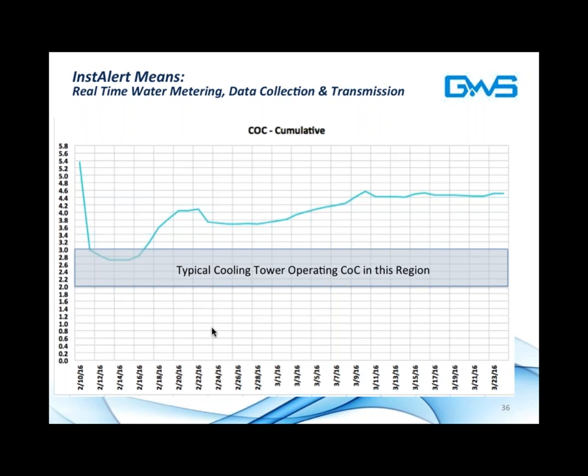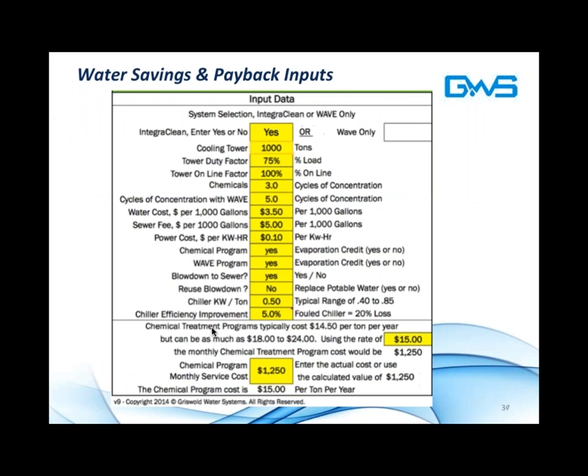And you can see that as the cooling season heated up and temperatures rose over time, we were able to further concentrate the minerals within the tower. So what this means ultimately is that we can track down to the gallon the amount of water consumed and discharged by the system. A significant advancement in the industry for water savings.